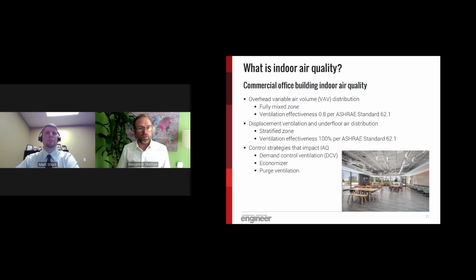You can also look at dedicated outdoor air systems that directly bring ventilation into spaces if you have concerns. In a lot of new office buildings, we might look at zone level equipment, a heat pump, a fan coil, or even a VAV system still, but we'll have dedicated ventilation brought to the space. There are several control strategies that can also impact indoor air quality.